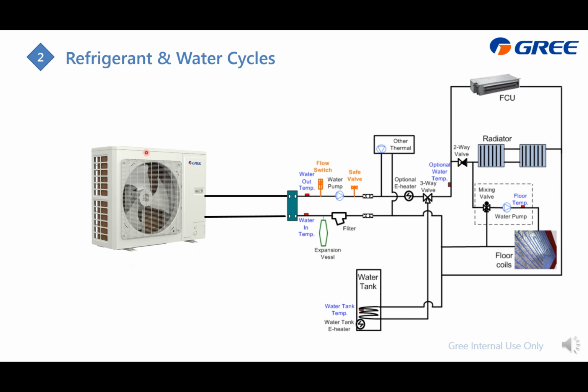It is a split type. So this is the hydro box, and with this one we have the water pump and flow switch, safety valve, and also the plate heat exchanger, the expansion tank, and a filter, which means this is the water in. And also this is the three-way valve to conduct the water either to the water tank for DHW or to the FCU, radiator or floor coils. And also just pay attention to where to install the other thermal and the optional e-heater.